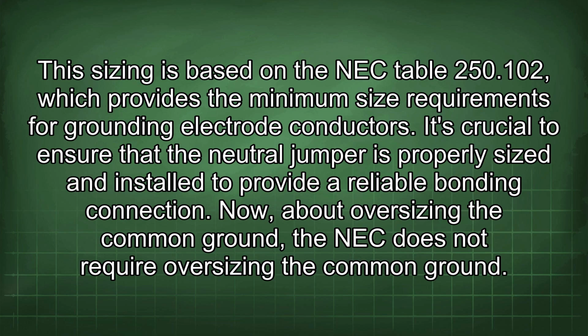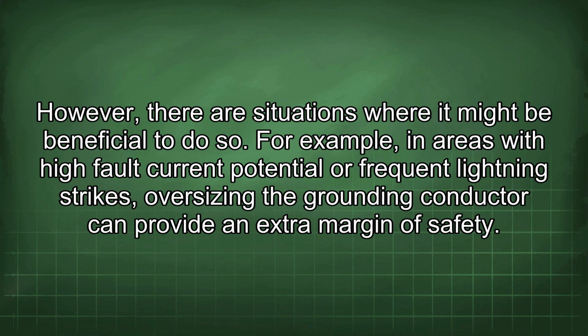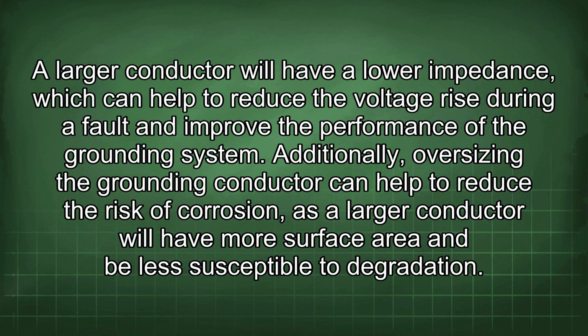Now, about oversizing the common ground. The NEC does not require oversizing the common ground. However, there are situations where it might be beneficial to do so. For example, in areas with high fault current potential or frequent lightning strikes, oversizing the grounding conductor can provide an extra margin of safety. A larger conductor will have a lower impedance, which can help to reduce the voltage rise during a fault and improve the performance of the grounding system.